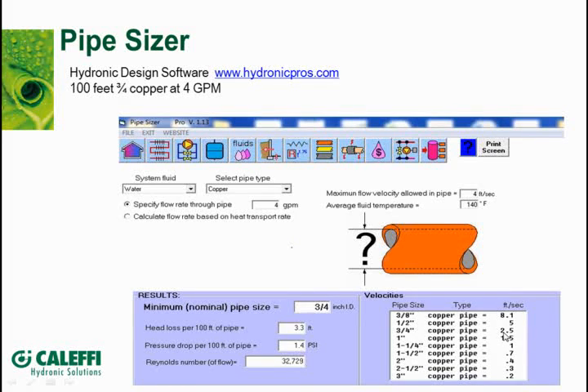You can see what our velocity is going to be, up there around 2.5 feet per second. So that's going to be sufficient. I'd like to see that a little bit higher, but that would be enough to push the air out of the system. So you can play with that. And also look at all the good information it gives you over here.